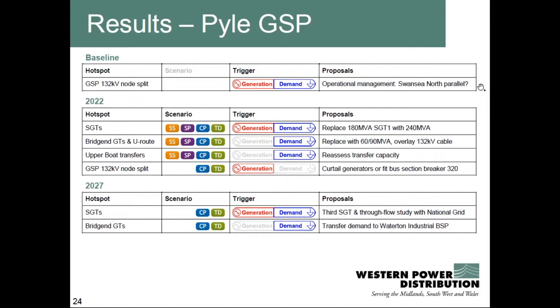Moving on to Pyle GSP, which supplies a coastal area between Swansea and Cardiff including the town of Bridgend. The GSP 132 kV node split is a key issue: normally the 132 kV bar at Pyle runs solid, but to maintain bus section breaker 220 it needs to be split into two separate nodes. If SGT1 were then lost on a fault, some of the 132 kV network could be back-fed by 11 kV and 33 kV bars of BSPs, risking overloading those grid transformers. This can be managed operationally, but by 2022 installing a third bus section breaker 320 at Pyle 132 kV board could help. SGT replacement is also triggered — SGT1 at 180 MVA would be replaced with a 240 MVA unit in 2022, and a third SGT may be required by 2027.